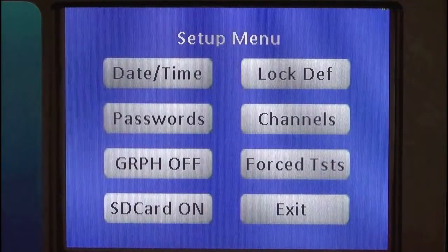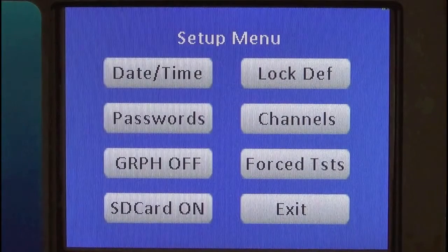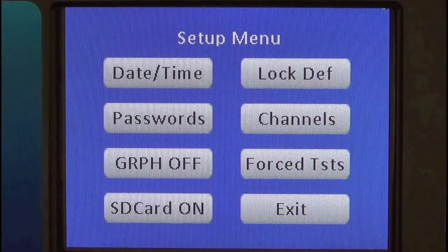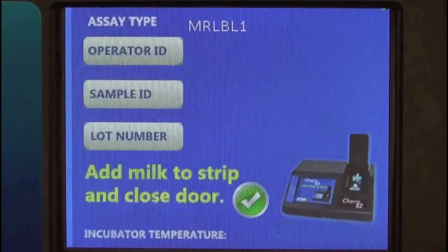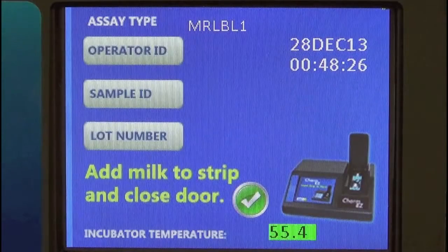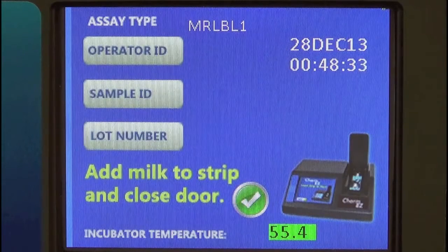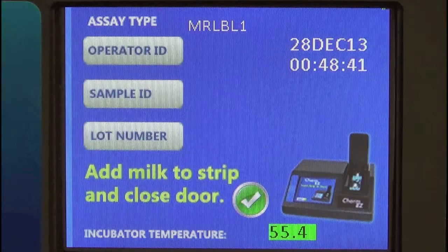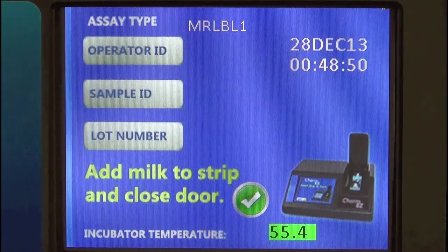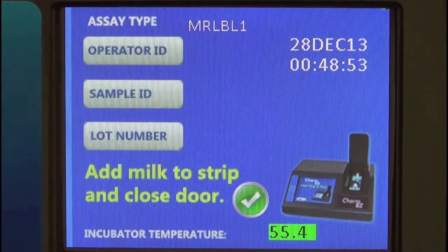Hit enter. And the first lock option you have is what's called lock default. So what this means is if we press exit and we go back to the main screen, it automatically loads the calibration parameters for the Emerald BL1 test. So the default channel on the EZ-Reader is automatically loading the calibration values for the Emerald BL1 test. This lock mode facilitates the reader so it automatically loads these calibration parameters, and the reader's not actually waiting those few seconds to identify the actual color on the end of the ROSA test.